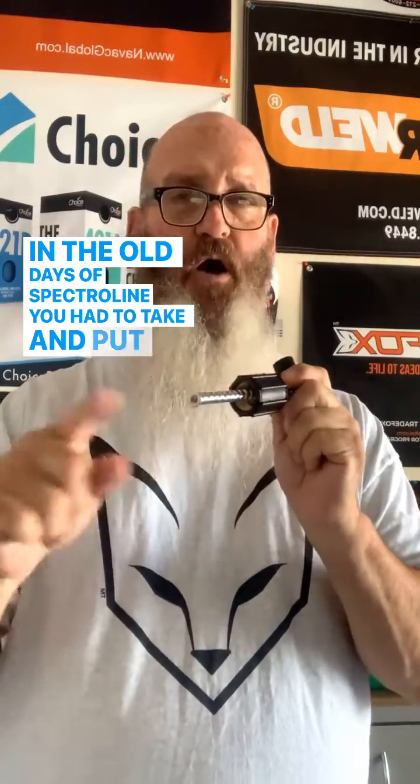Here's why I like this kit. In the old days of Spectroline, you had to take a hose, put it into the system, and chase refrigerant behind it — it went everywhere, it was a huge mess. Now you put the stick in, close the system down, and turn this handle to inject it in very slowly.